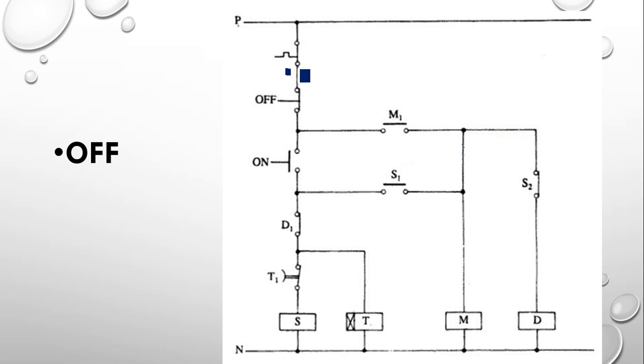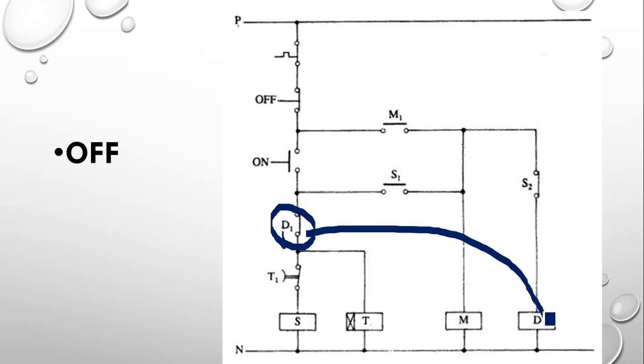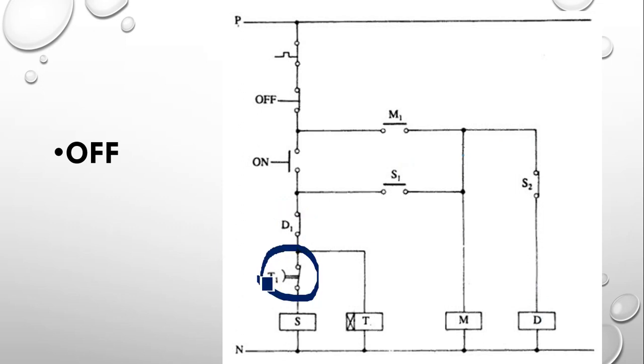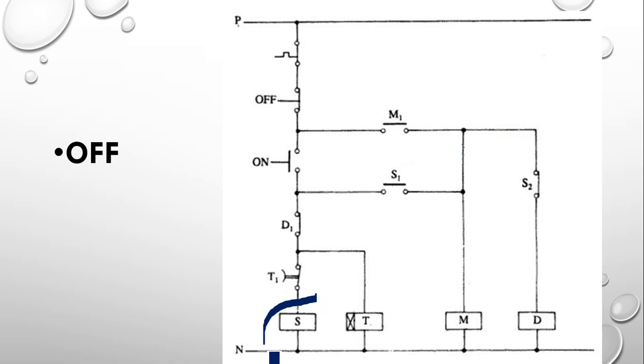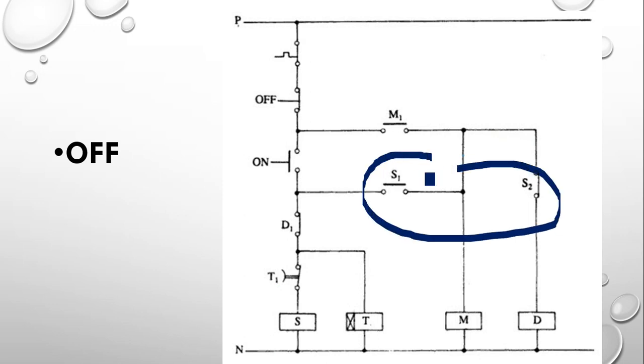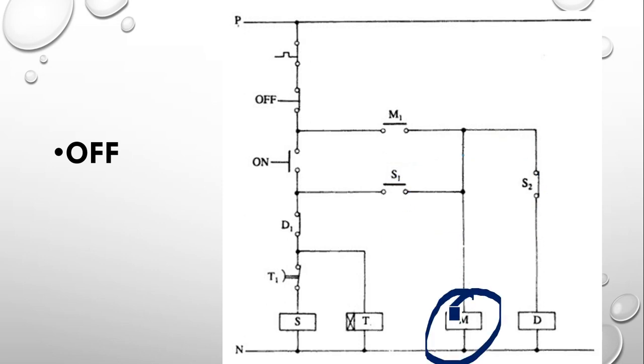Now the control circuit: components include a normally closed trip contact from the thermal overload relay, a normally closed off button, a normally open on button, D1 the normally closed auxiliary contact of the delta contactor, T1 the normally closed timer contact (new addition compared to semi-automatic), a timer coil, an NO auxiliary contact of the timer, the star contactor coil S with contacts S1 (normally open) and S2 (normally closed), the main contactor coil M, and M1 its normally open auxiliary contact.